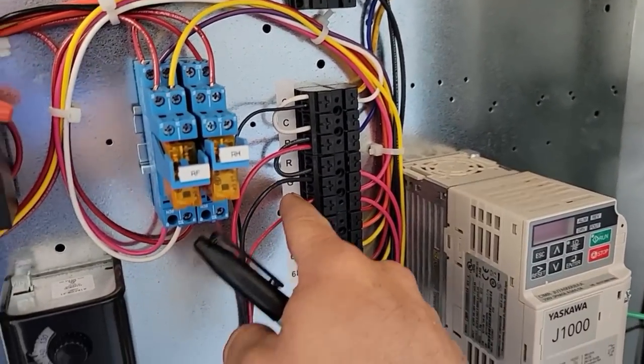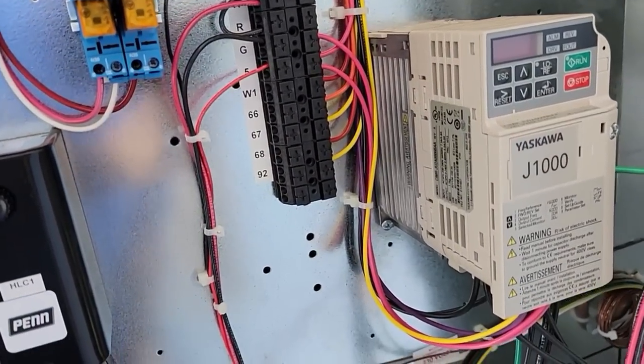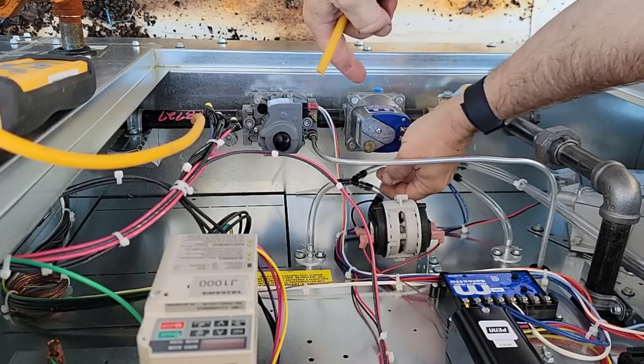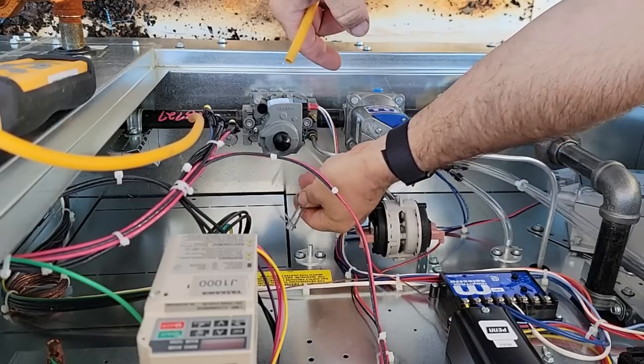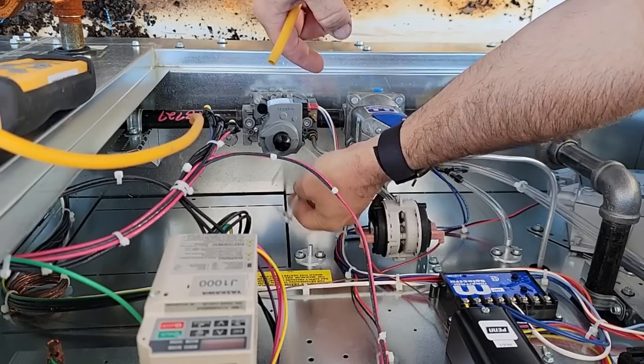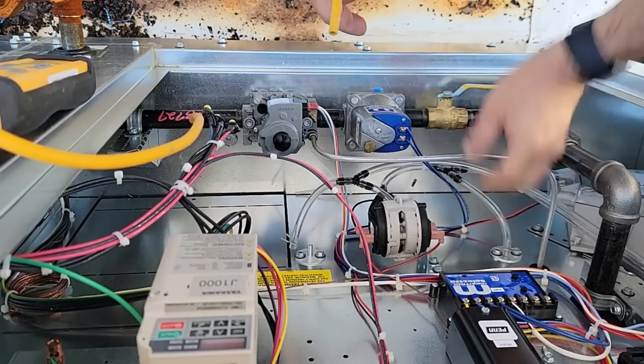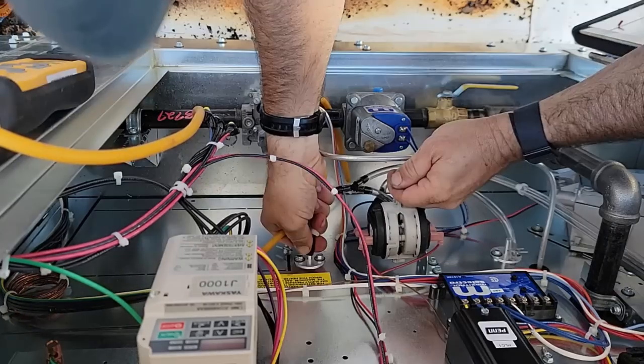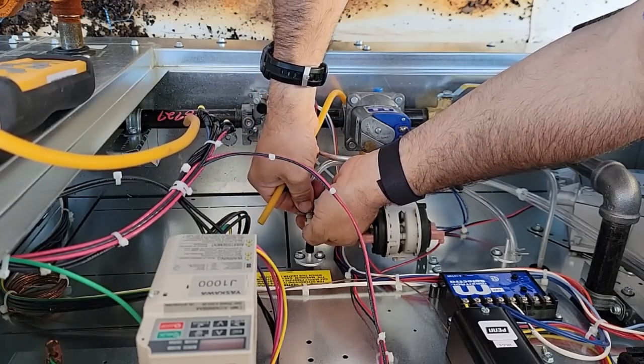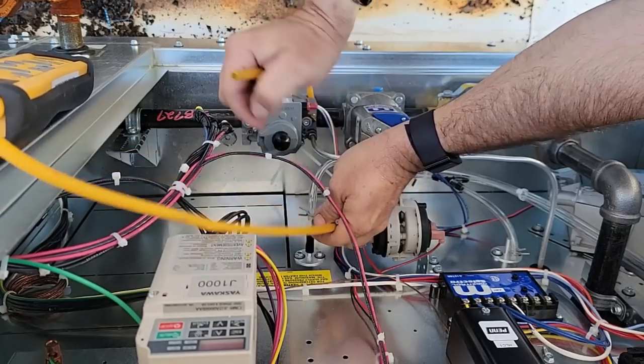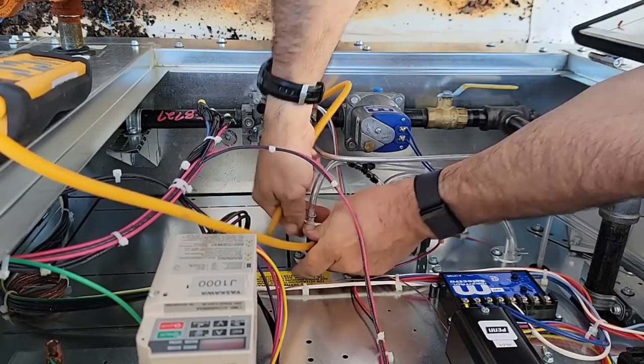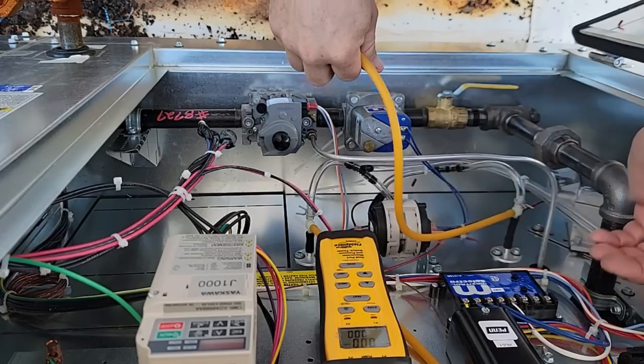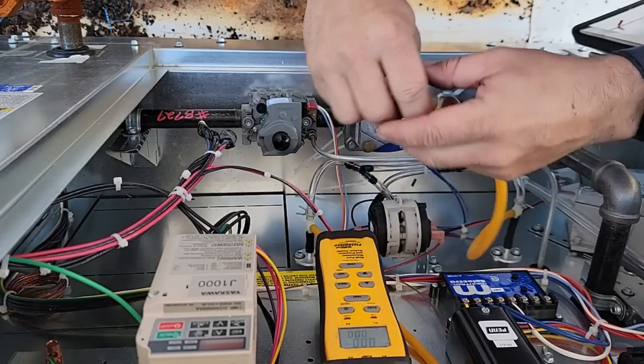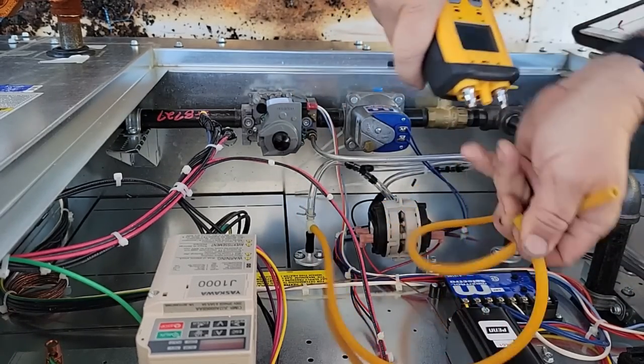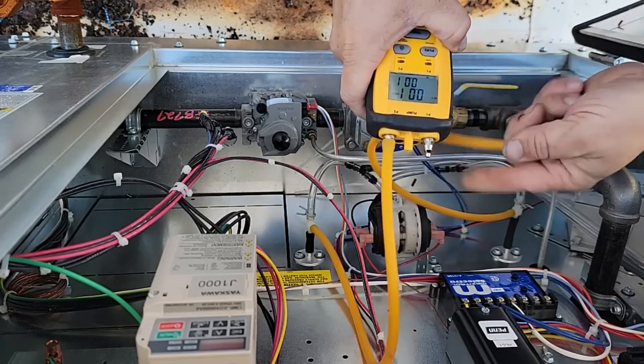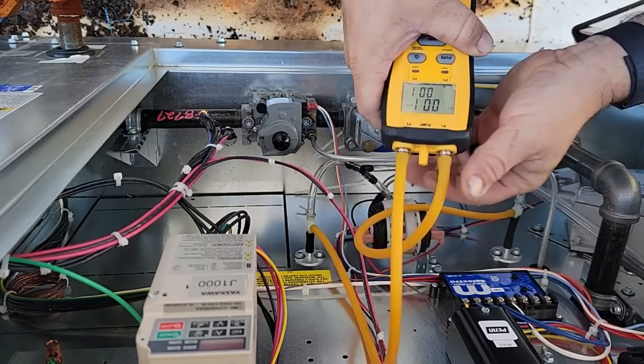Also, this is your wiring for bringing on the burner, which I believe we have to hit the W1 there. What we can do, I've got T's we can put in line with this and just check it out. We can go right there and there. We'll just put our T's in there like that, hook that on there, and hook the pressure port thing on here. By checking it this way, you're checking it across the whole circuitry of the pressure switches to see whether or not there's an issue with any type of leakage in the hoses or in the diaphragms of the switches. So we're gonna kick it back on.